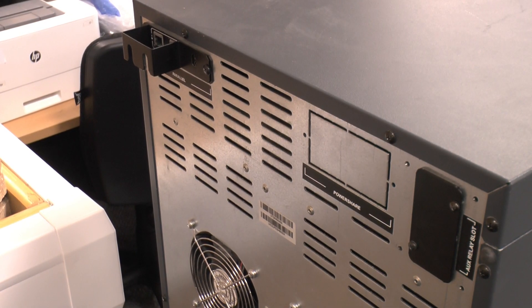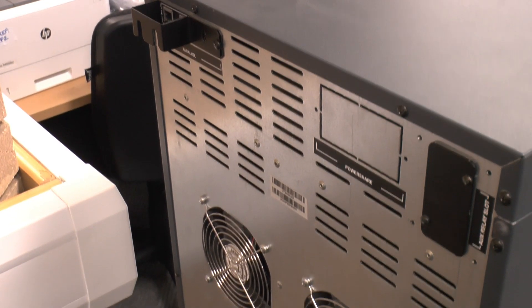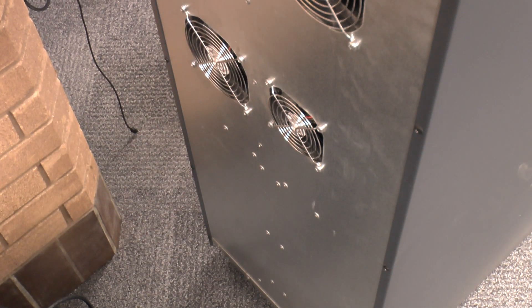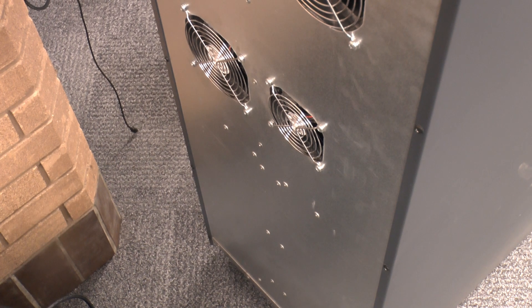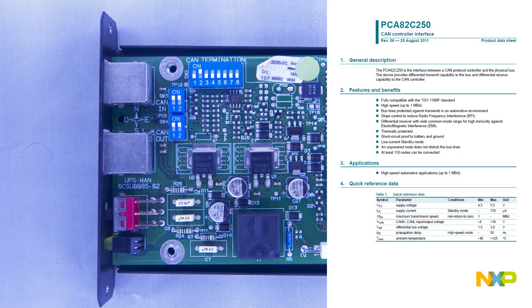Round the back there's a parallel communications module which allows the UPSs to run in tandem, with provision for another expansion card, and fans for the various modules inside. The parallel comms module doesn't have much on it — the main features are a bunch of optocouplers and an PCA82C250 CAN bus controller to deal with communication between the UPSs.